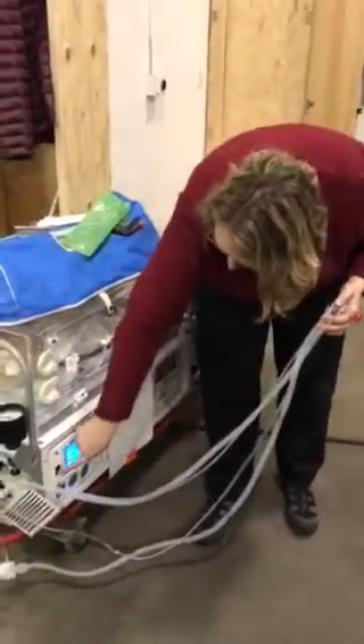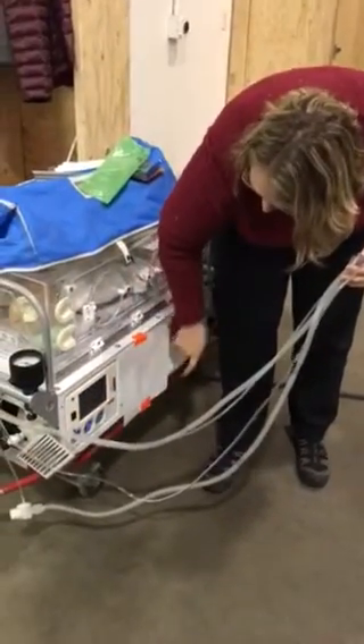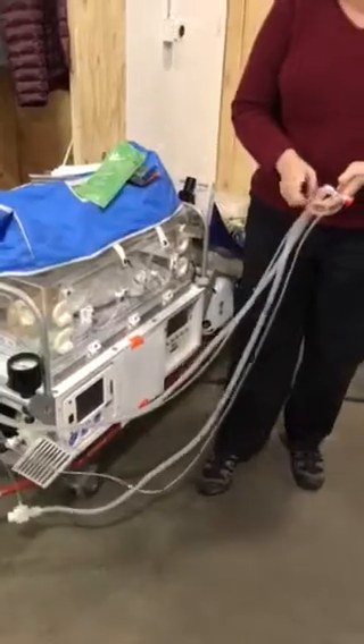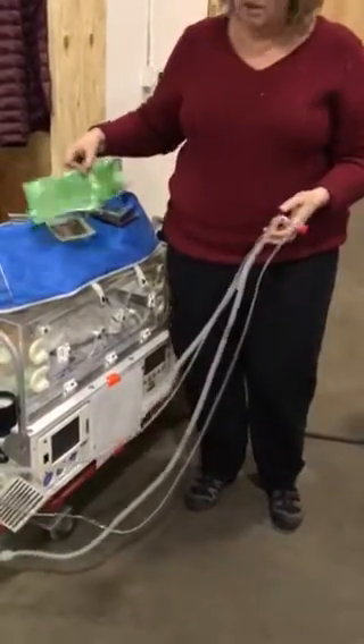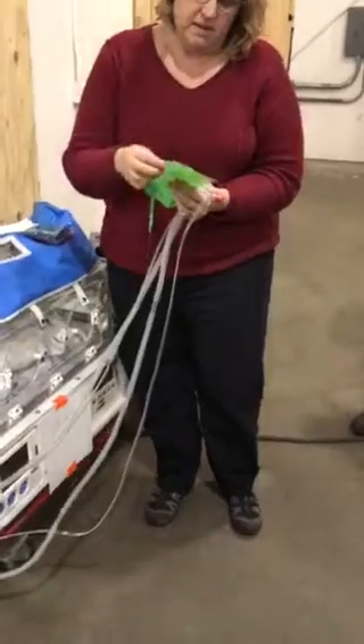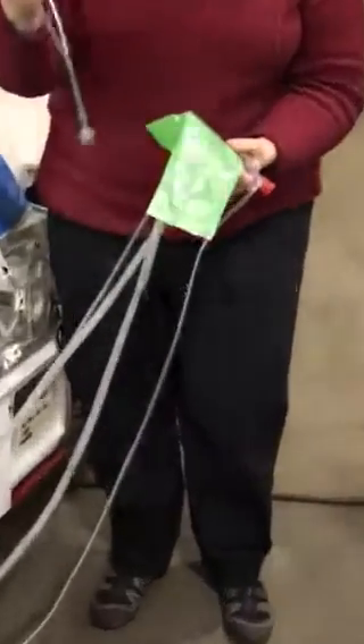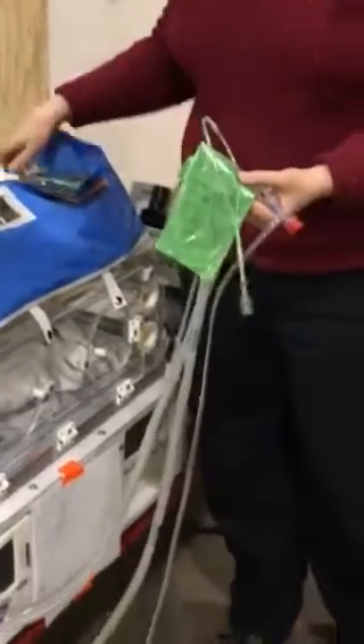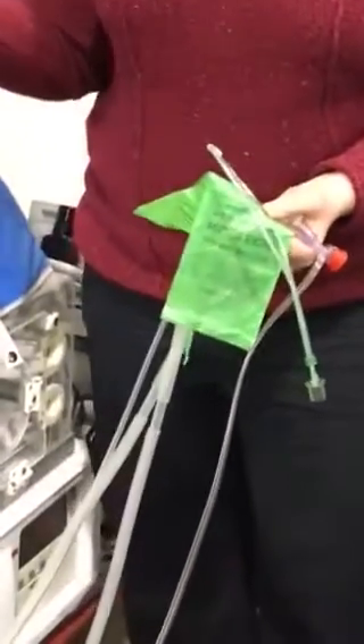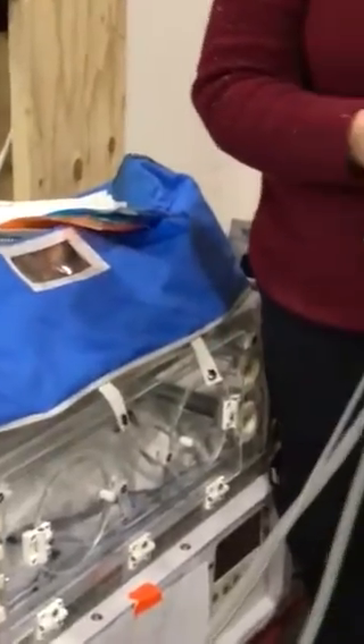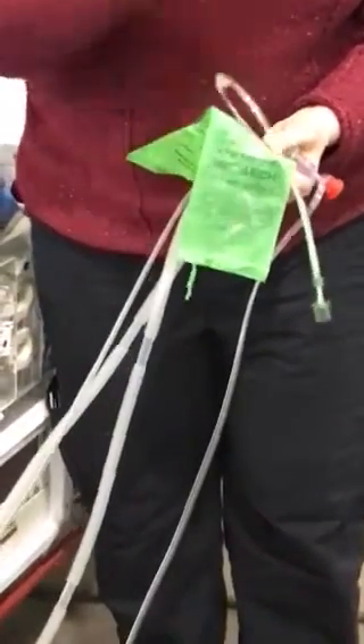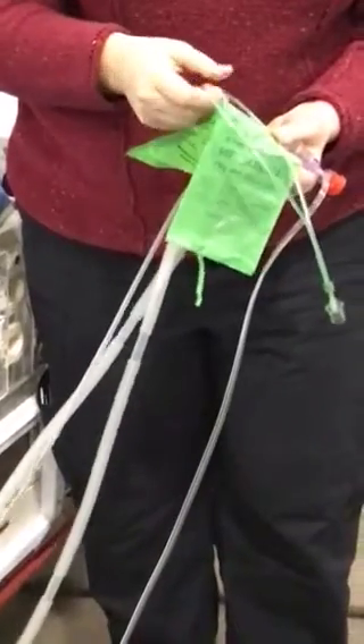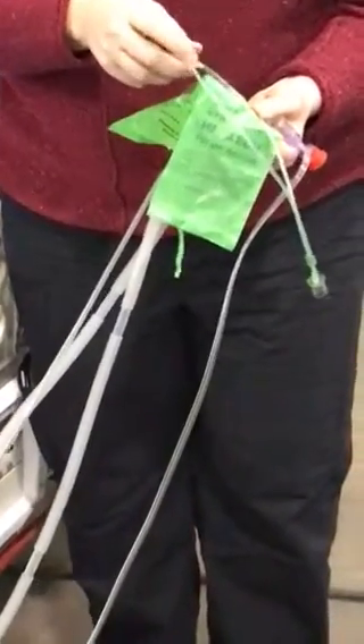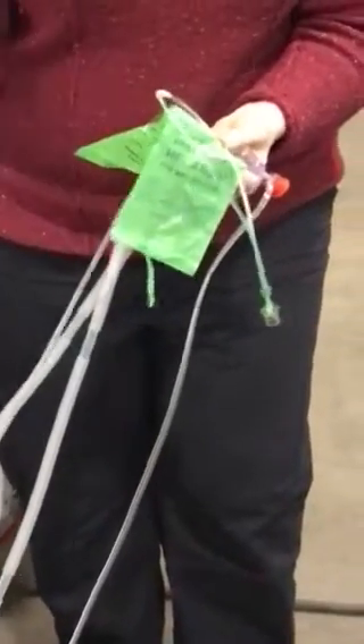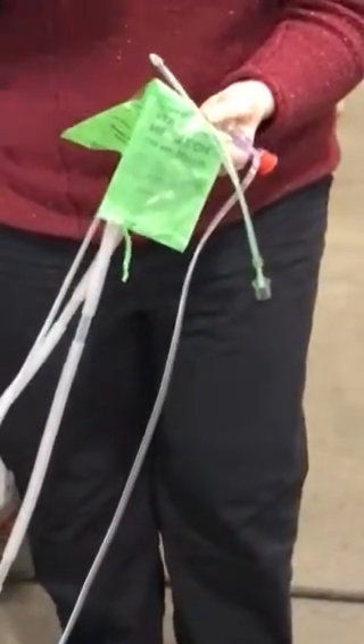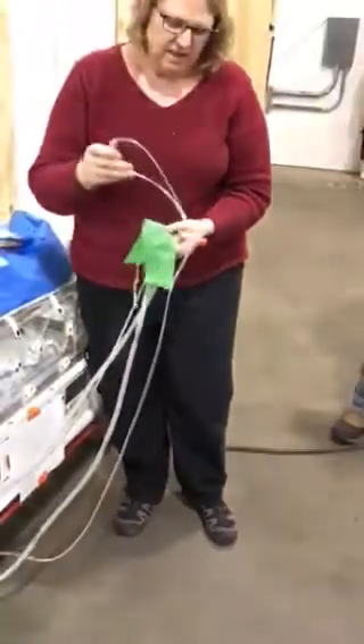Let me turn it off. We have high flow cannula that we're using, or we can use CPAP with the ventilator. It's essentially a high flow, but it's this RAM cannula, and they're in the bags as well. And this is what they look like. Okay, and there are different sizes of cannulas for those babies. But the idea here is you're giving regulated controlled CPAP, but it's not occluding the airway. It's not designed for that. It's not approved for CPAP, so it's essentially high flow, but you're giving them CPAP through the ventilator, so you know that it's regulated. Does that make sense?